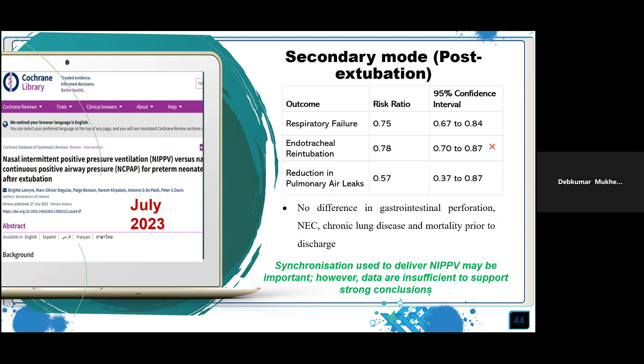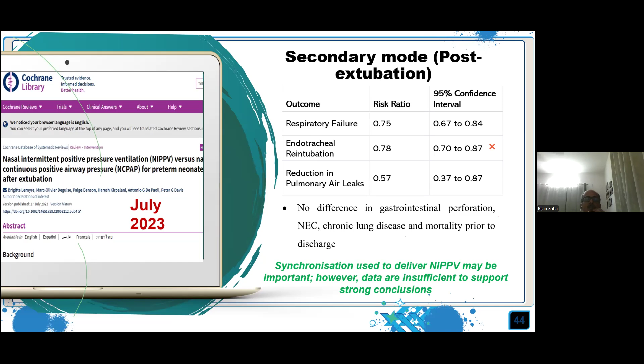as a secondary mode. But the problem is that if you want to provide NIPPV, you need a ventilator. A ventilator costs around 10 to 12 lakhs, but in 2 to 3 lakhs or 4 lakhs, you can get a CPAP. So with the cost of one ventilator, you can buy 2 to 3 CPAP. So if you have got the facility for NIPPV, you can use NIPPV both as a primary mode or as a secondary mode. Next slide.